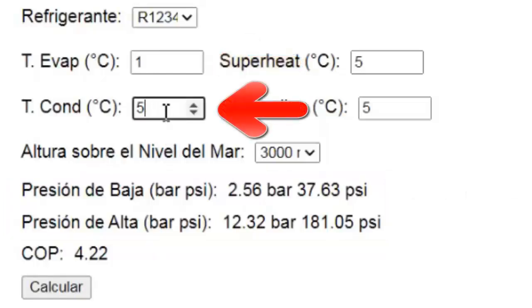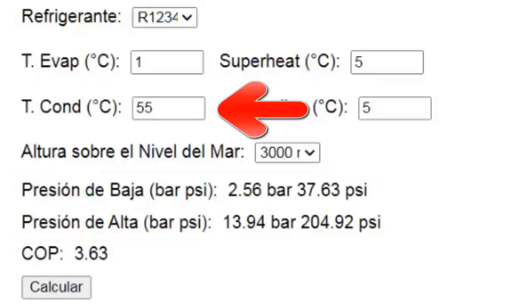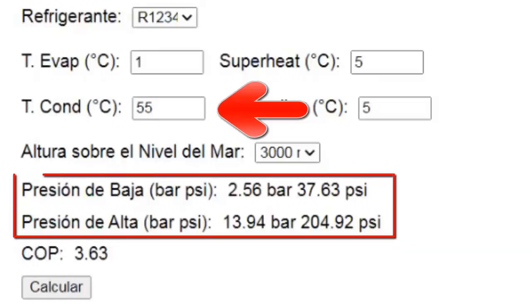During that same acceleration, the refrigerant gas being pulled by the compressor flows more rapidly toward the condenser. This increases the pressure and temperature in that area, raising the overall condensing temperature. In this case, we'll estimate the condensing temperature by adding 25 degrees Celsius to the ambient temperature, observing the following pressure.